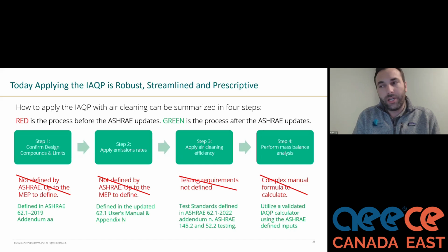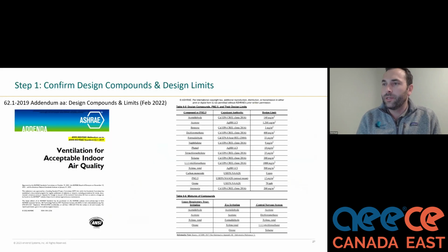And so what ASHRAE has done is taken a lot of these things that were up to the MEP to define and said, no, we'll give them to you. So based on space type, ASHRAE 62.1 2019 Addendum AA gave us allowable limits of specific design compounds. They also gave us the emission rates of those contaminants. And further, they also gave us testing standards for defining air cleaning efficiency. Last is they gave us a calculator to make all this super easy and give us an easy button there.